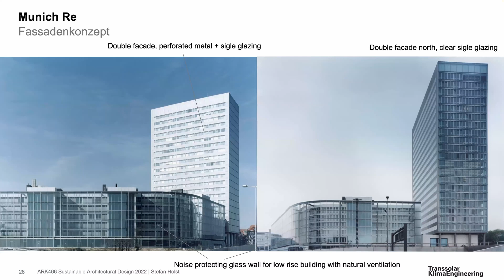The Munich Re high-rise building in Munich, together with Alman Sattler-Wapner, finished in 2003. And the idea was to have a facade concept that allows natural ventilation, that protects the shading from the wind, because we have strong winds in Munich, and that provides operable elements at all office spaces in all directions, for people to naturally ventilate. And they can ventilate the top window, which then generates some preheating of incoming air by its solar radiation. And they can open a lower window here in summer when you directly want this ventilation coming in through this perforated metal that is part of the exterior envelope.